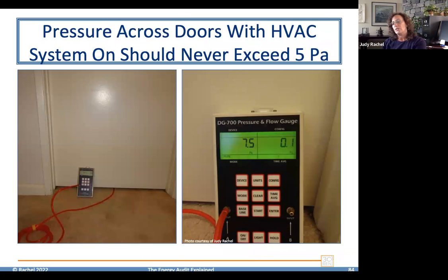Then there are pressures across doors. When we have the heating and cooling system on, air needs to be able to get back to the returns. So we really want our systems to never cause more than 5 pascals of pressure difference if we have to close a door to a room. 3 to 5 is good. This is an easy test to do with the manometer: go around to the various doors, close them, and see what the pressure is across the doors.